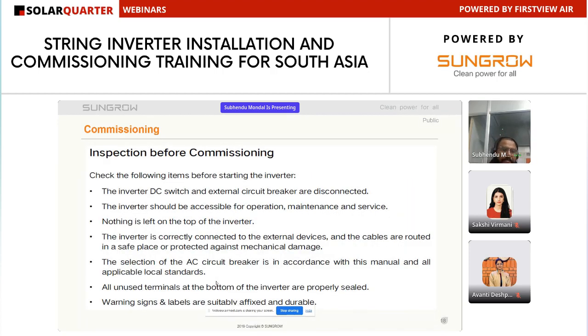Inspection before commissioning. Check the following items. We need to check the following things before commissioning the inverter. The inverter DC switch and external circuit breaker should all be disconnected. The inverters should be accessible for operation, maintenance and service, in a free place. We have to ensure nothing is left inside or on top of the inverter during termination work. The inverter is correctly connected to the external devices, and cables are routed safely, protected against any mechanical damage.